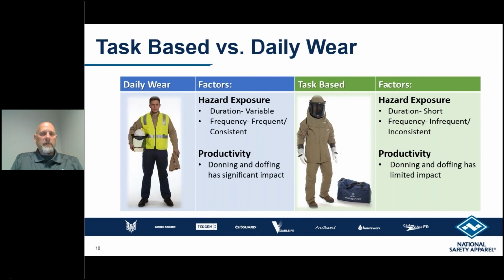Typically what happens is, since Cat 1 and Cat 2 are just shirts and pants, very similar to any work clothing somebody would wear anyway, Cat 1 and Cat 2 clothing oftentimes will be daily wear. People who work around these types of hazards will wear that clothing to work all day, every day. And when they get into a panel that requires head-to-toe PPE, they will put on the balaclava with the face shield and put on their voltage rated gloves.